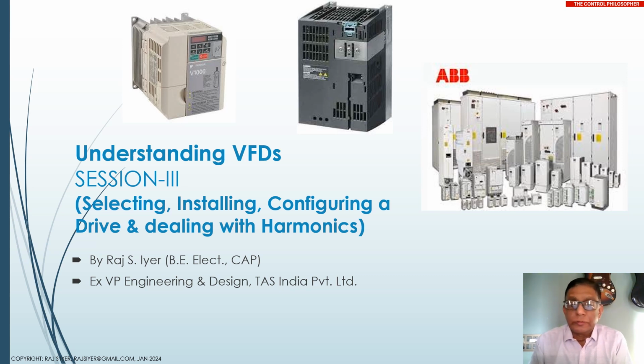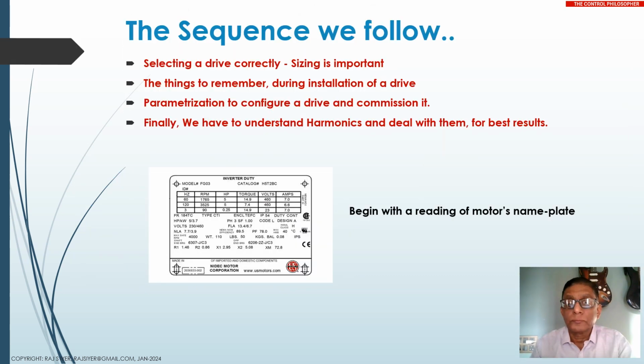Okay, so today we will understand problems like harmonics, and finally we will see how to actually configure a VFD for use. Okay, let's get going. See, configuring a VFD for use or installing a VFD is less complicated than what most people think. Basically, you have to install it correctly with proper earthing and all that. And then the most important thing is to have the motor nameplate data readily available with us.